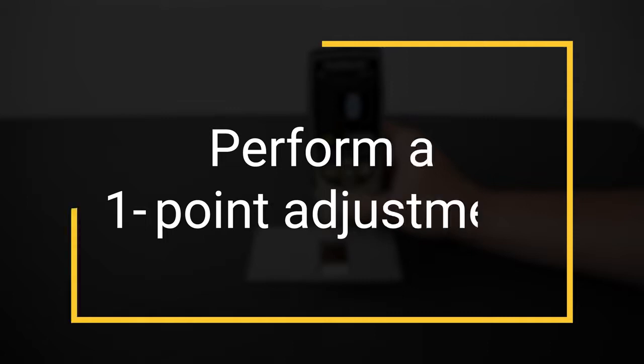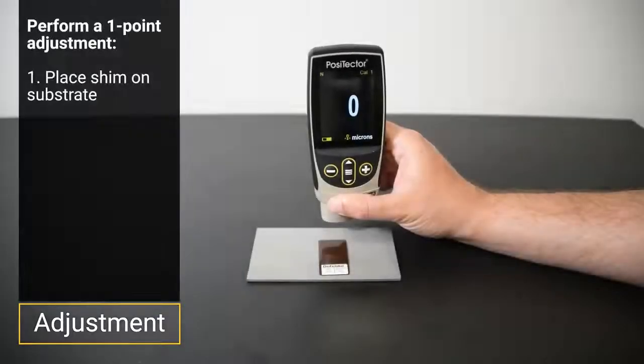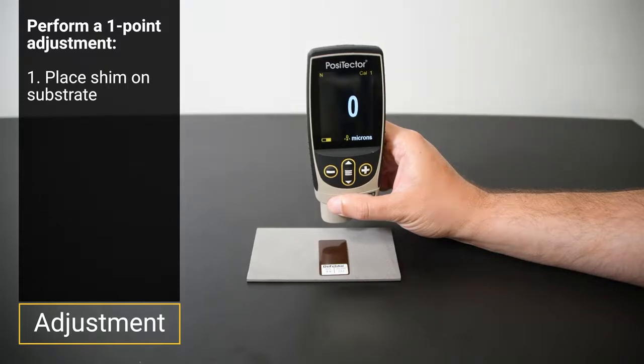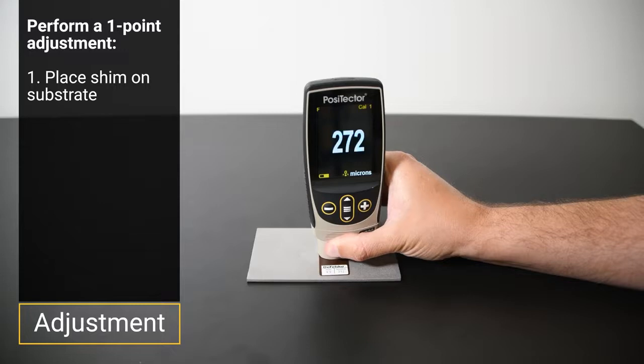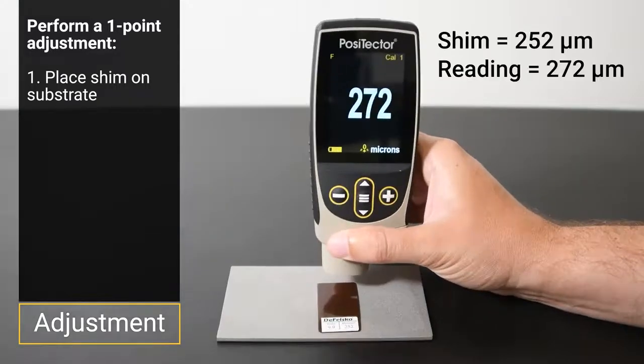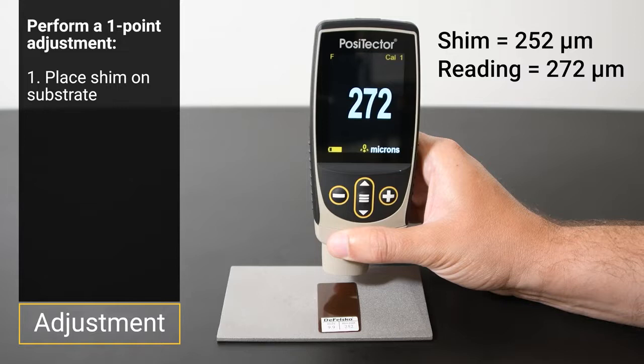To adjust for surface profile, a one point adjustment is required. Choose one of the included shims that is near the expected coating thickness and place it on the uncoated blasted substrate. The instrument will typically read higher than the thickness of the shim, reflecting the difference between the magnetic surface and the peaks of the profile.